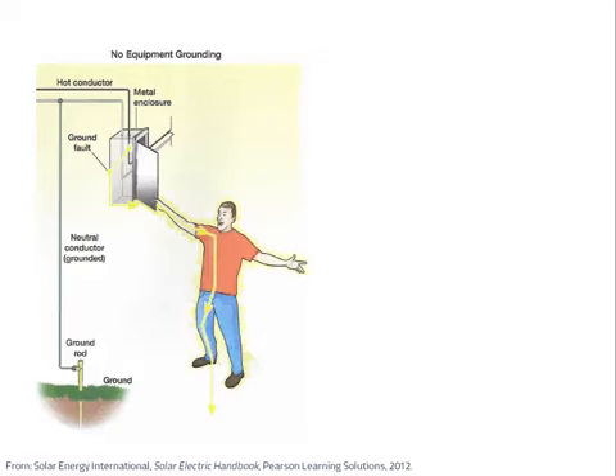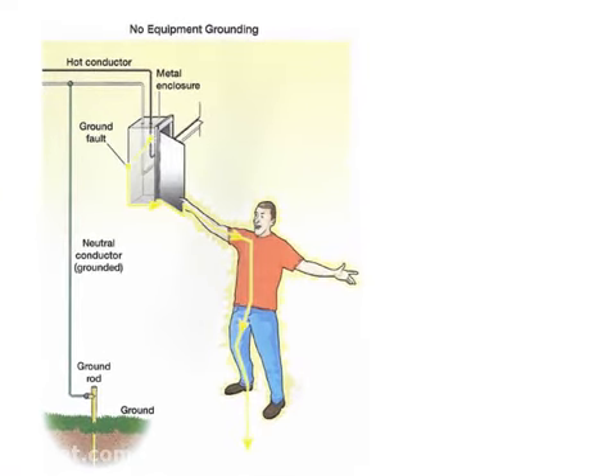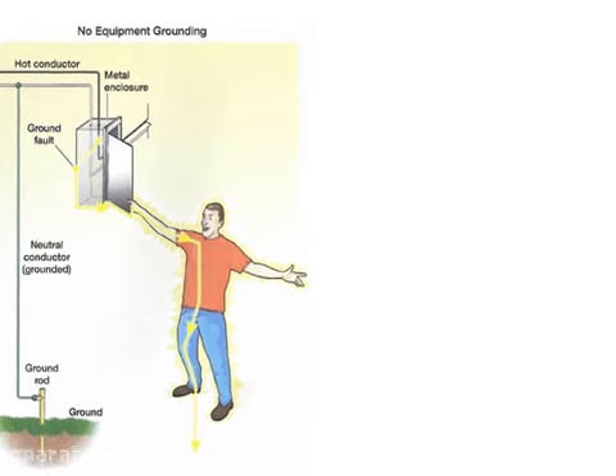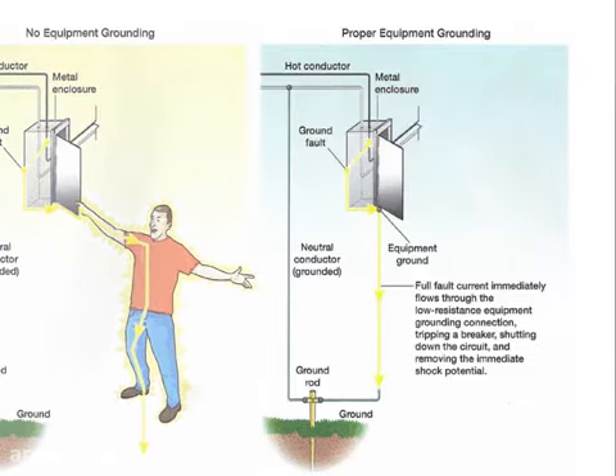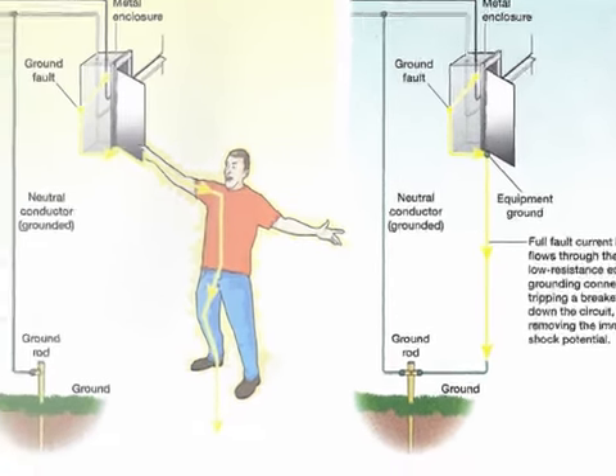This figure shows that if a hot or energized wire comes into contact with an ungrounded metal enclosure, somebody touching it may get an electrical shock. However, if the enclosure is properly connected to ground, as shown here on the right, the current from the enclosure to ground causes a circuit breaker to open. This turns off the circuit before someone comes near.